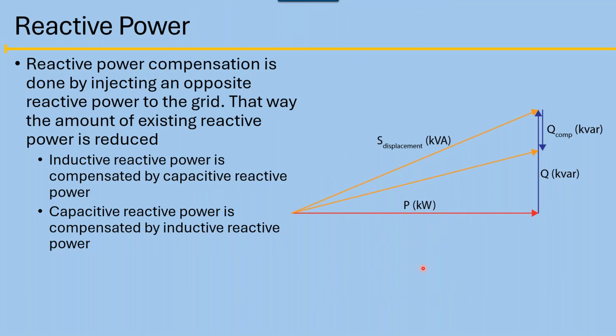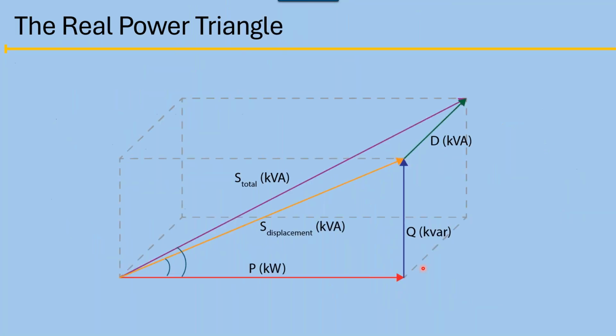The way we really should show the power triangle is as a three-dimensional equation. Here's kW, here's kVAR, and this we call displacement. And this is showing the harmonics. After I get through with all these, in one of the slides I'll simplify it down to current and show you the difference. So here's your displacement kVA, and here's your real total kVA, which includes the harmonic component. Why they never showed us this as engineers, I'm shocked, because this is really the true equation. When I saw it, it blew my mind.